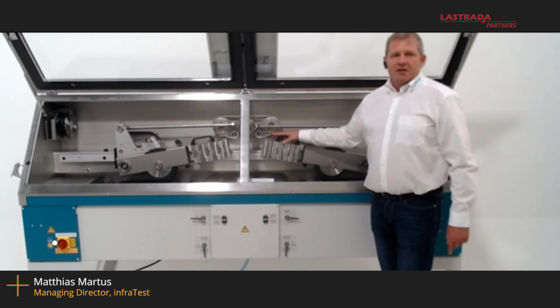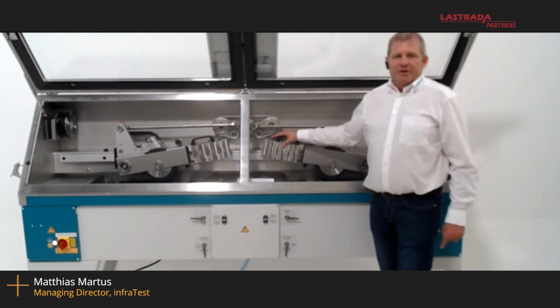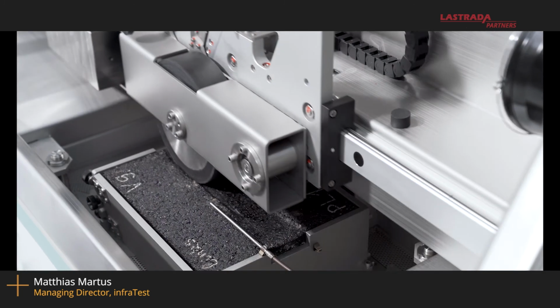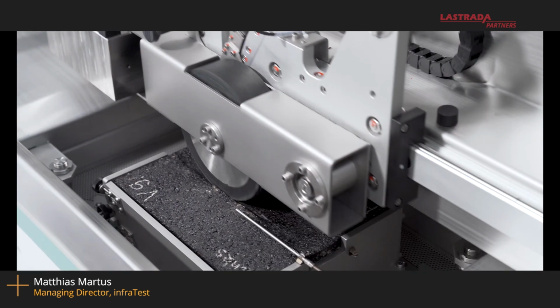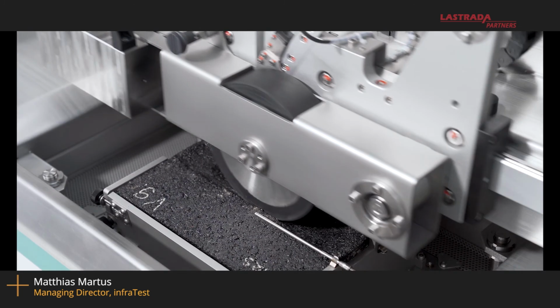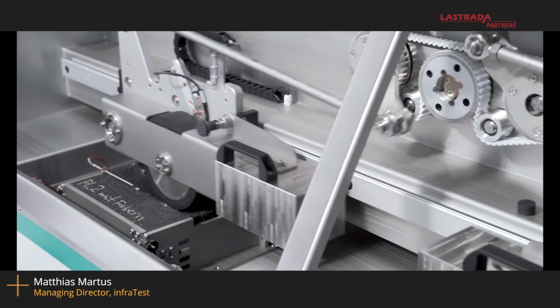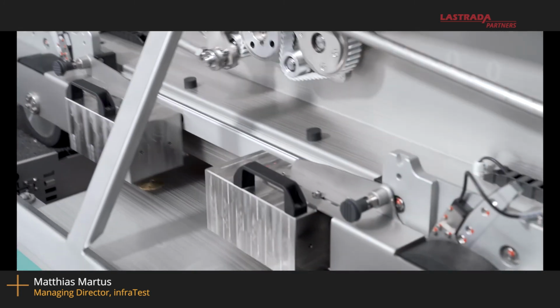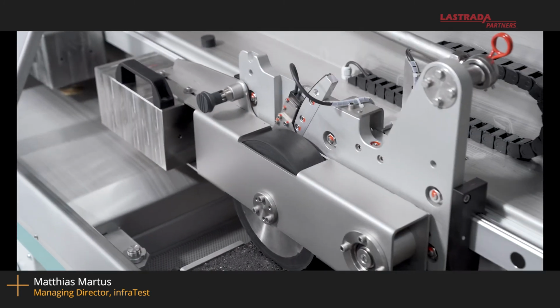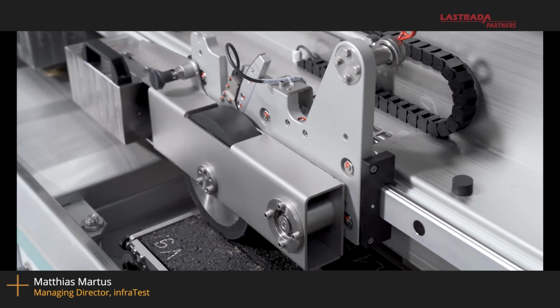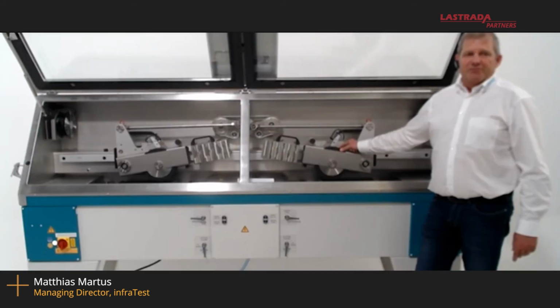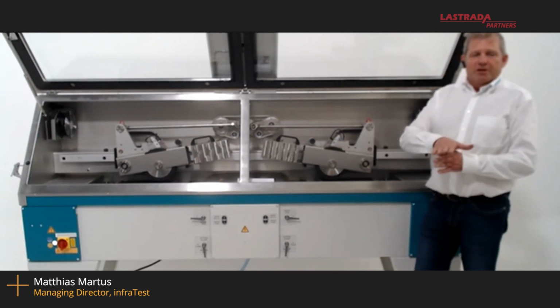You can increase the weight until you have double the weight in it. We also have smaller wheels. At this point, we have the standard size wheel, which is 50 millimeters. We also have it in half size and 2/3 size, so we have it in 25 and 38 millimeters wide. So you can play with the pressure on the gap of the sample.